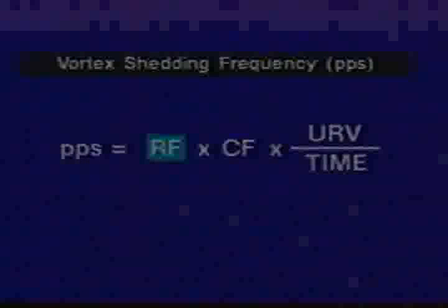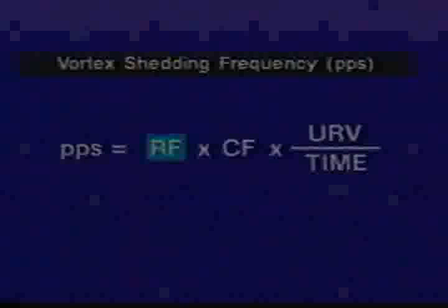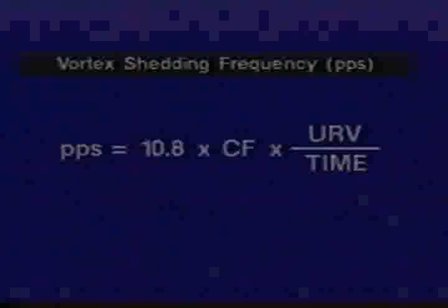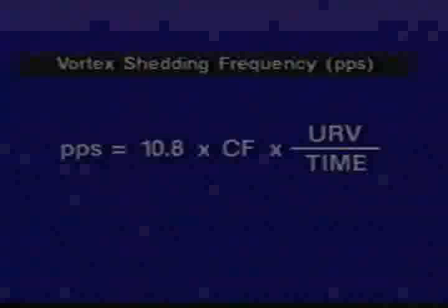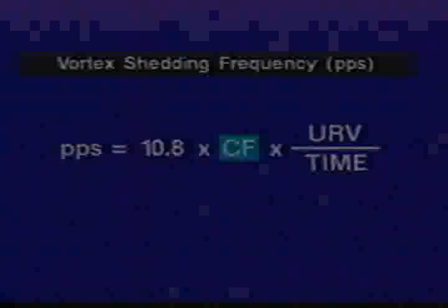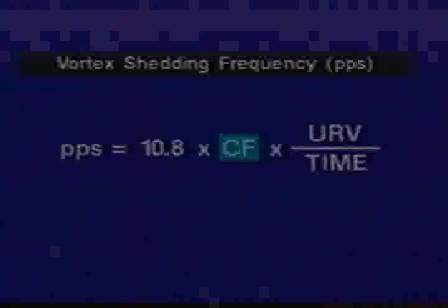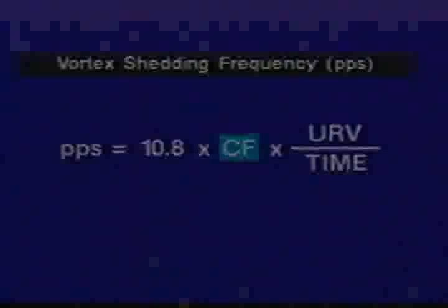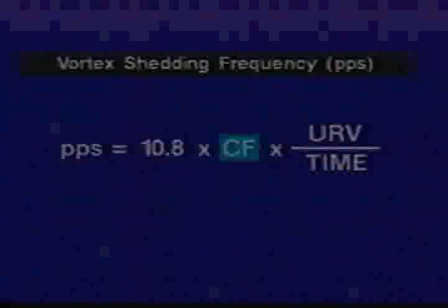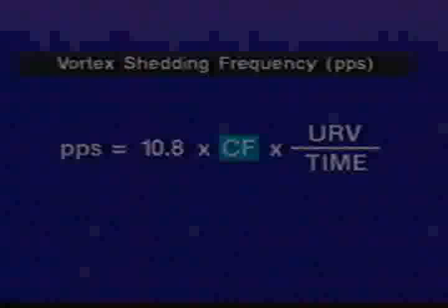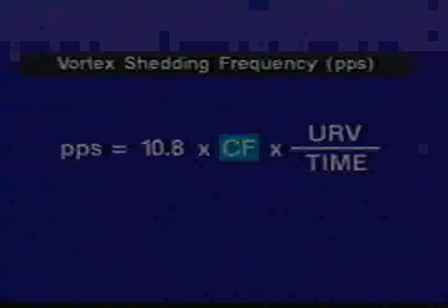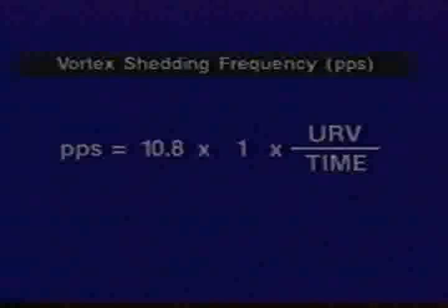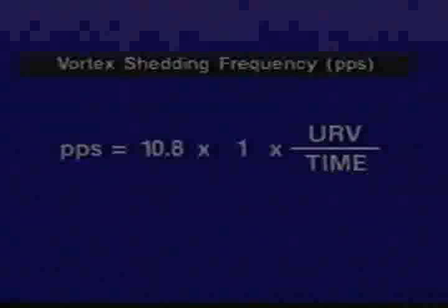RF stands for reference factor. The RF can be found on the transmitter's data plate. The RF is represented in pulses per US gallon. Here, 10.8 is the RF. The CF, or conversion factor, is a number that comes from the conversion factor table found in the manufacturer's instructions. The CF converts the RF to actual volume or mass flow rate units. Let's apply a conversion factor of 1 to this example.